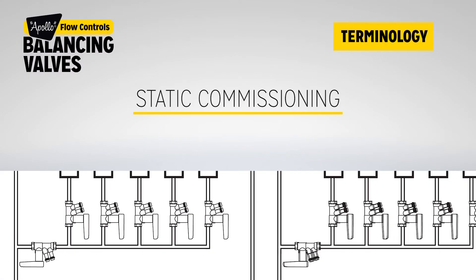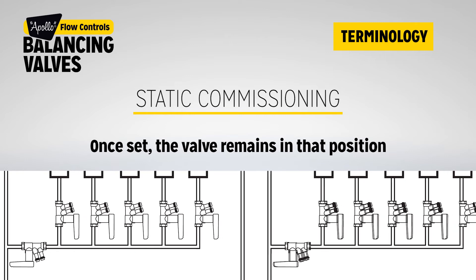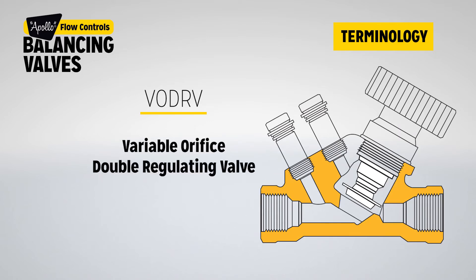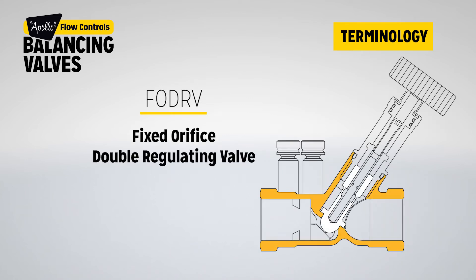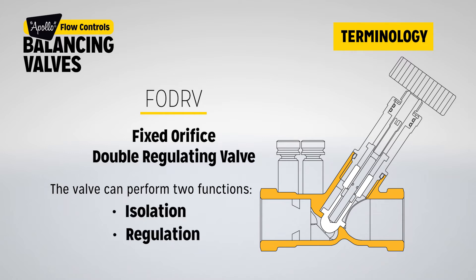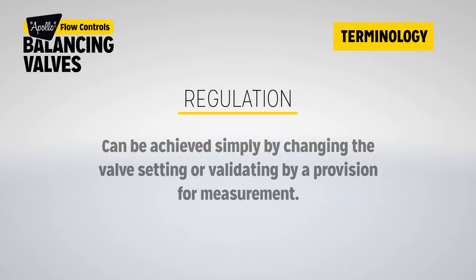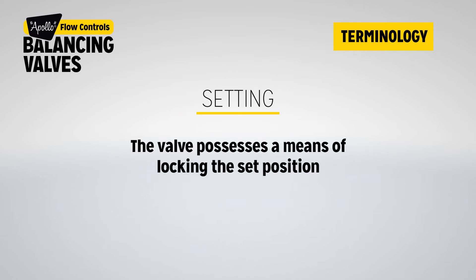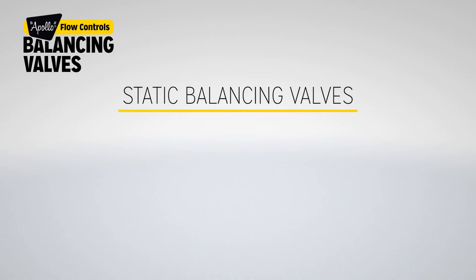Static commissioning terminology: once set, the valve remains in that position. DRV: double regulating valve. VO DRV: variable orifice double regulating valve. FO DRV: fixed orifice double regulating valve. The valve can perform two functions: isolation and regulation. Regulation can be achieved simply by changing the valve setting, with provision for measurement. The valve also possesses a means of locking the set position.